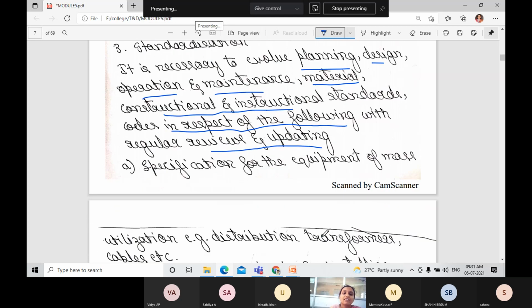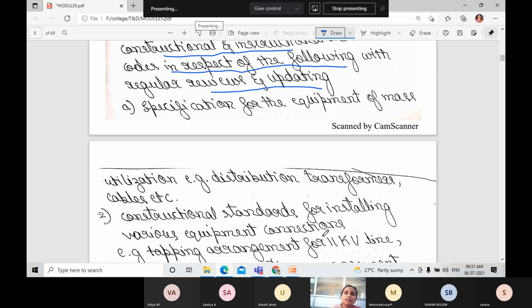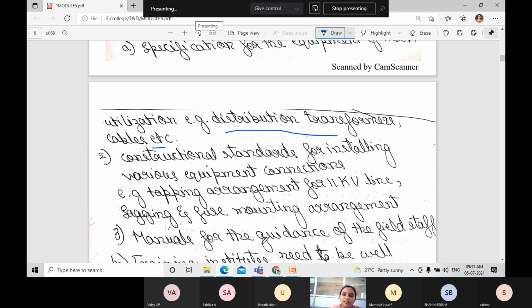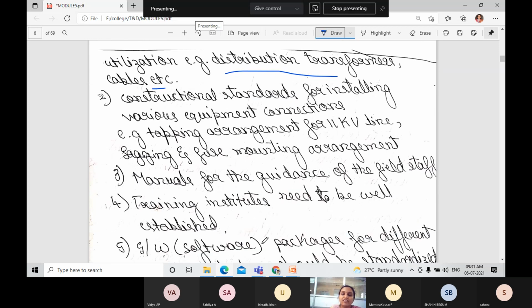Next is the equipment list and its utilization, for example distribution transformer, cables, etc. Next is the constructional standards for installing various equipment connections, nothing but tapping arrangement for 11 kV line, and sagging and fuse mounting arrangement. Next is a manual for the guidance of the field staff. If we are using a control panel, if we are using SCADA, any equipment, even before going to an experiment in the lab, you check the manual, right? What is the given procedure for that, and also what equipment is available in that experiment. You go through the manual, next you start the experiment.